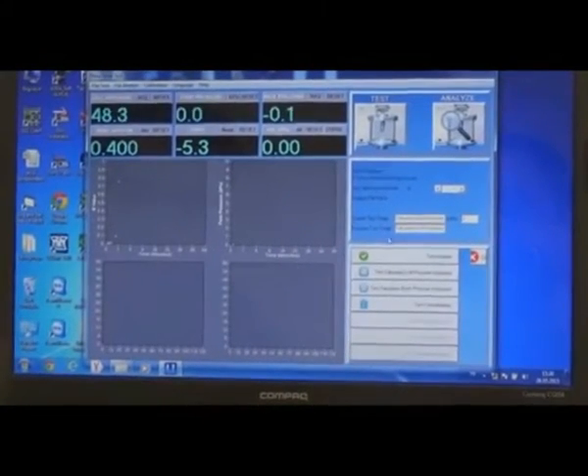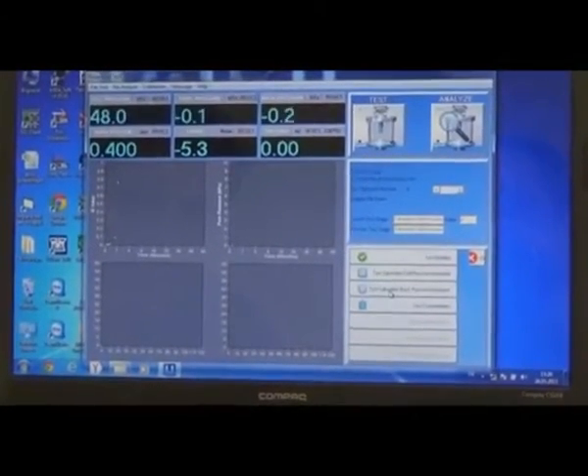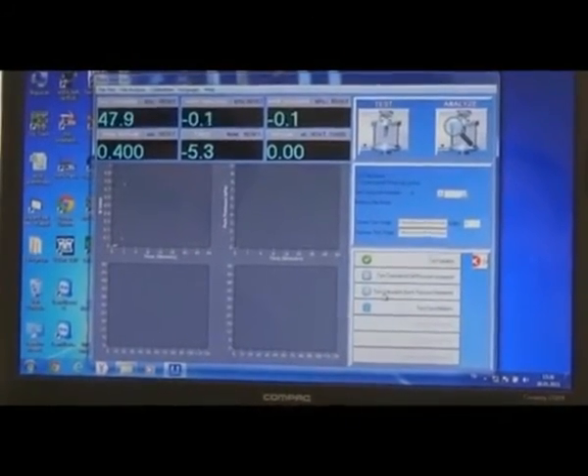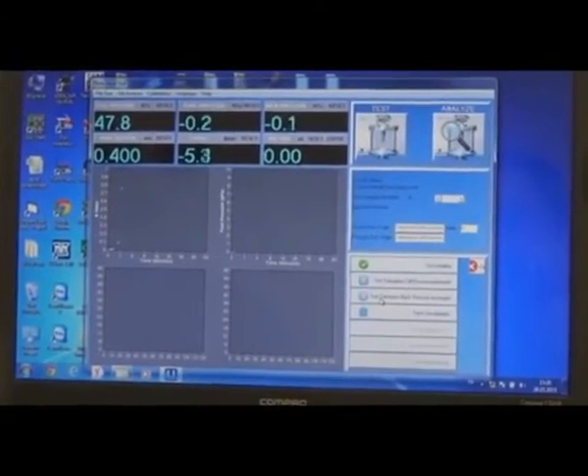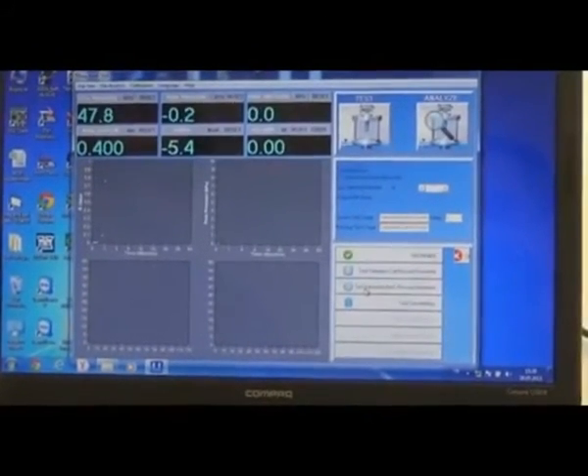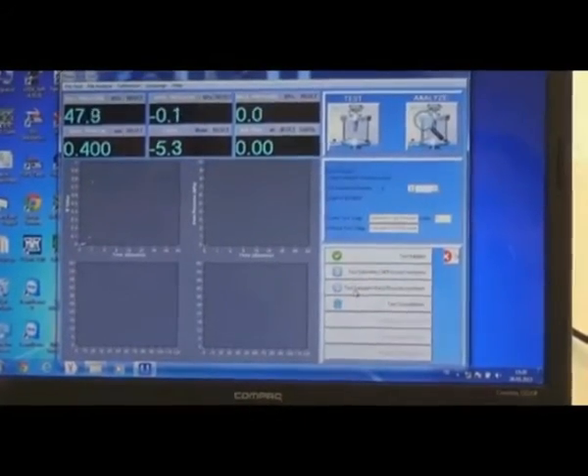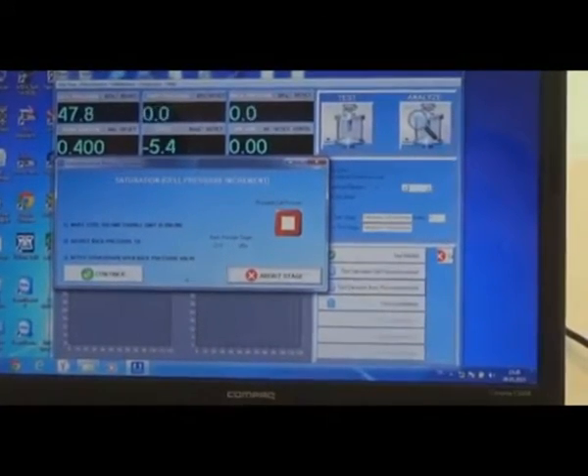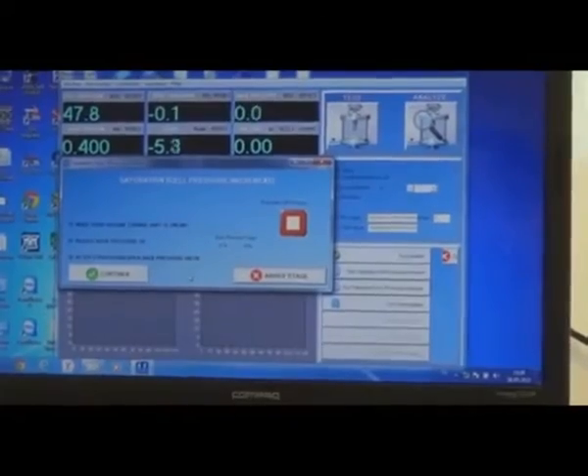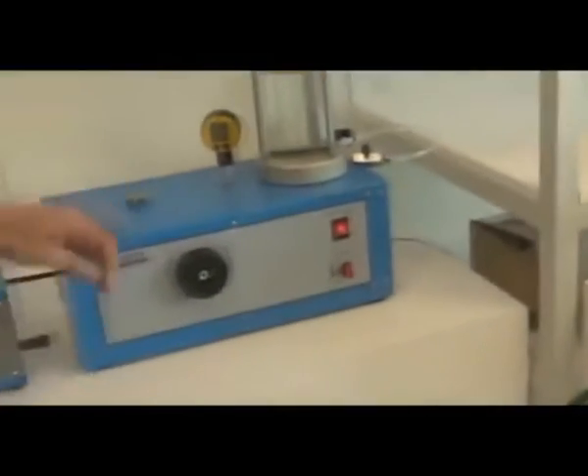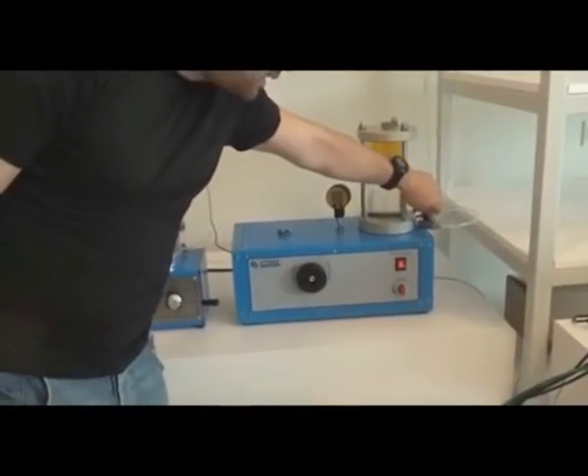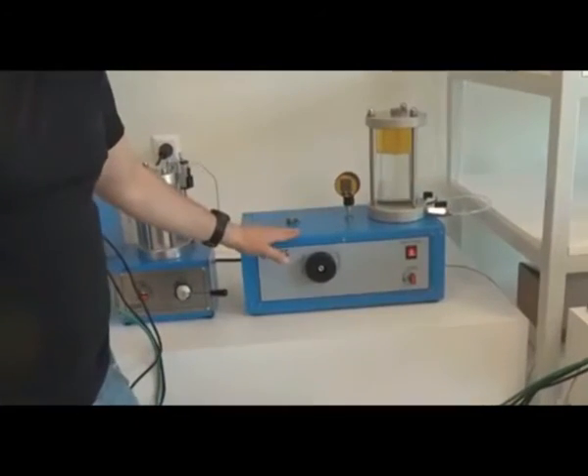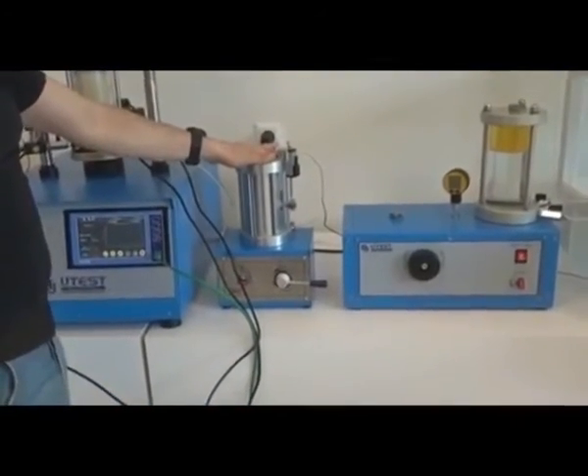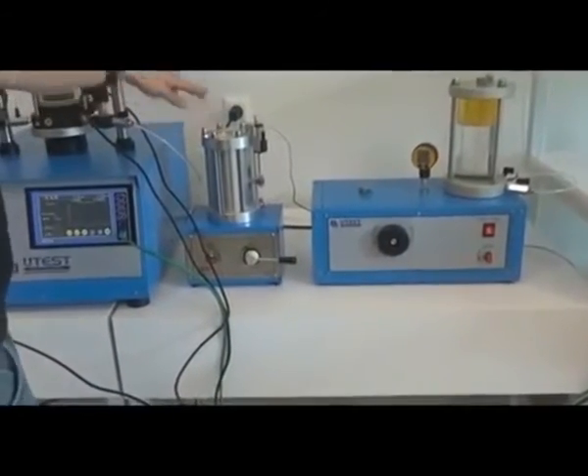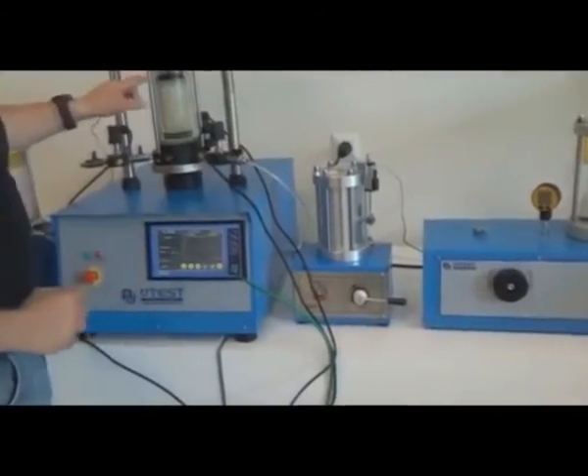And test again. Now I'm going to click the test saturation back pressure increment, where I'm going to do the same procedure for the back pressure, which is inside the specimen. Now I'm going to arrange the pore pressures again. With this constant pressure unit, I'm again opening the valve, which is connected to the volume change, and then connected to the back pressure from the top cap.